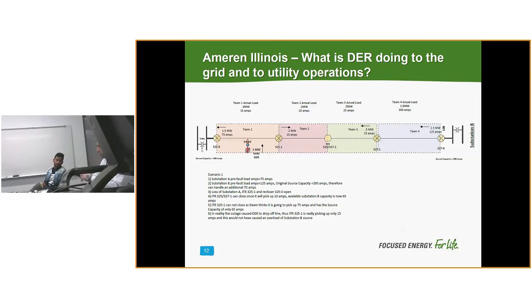And in particular, it used to be an anti-islanding rule or standard. The idea there is when you have an outage, you don't want all these DERs to still be connected to the system and trying to provide energy to the system. That creates an unsafe situation for workers on the grid. That's one. So anytime you see a disturbance on the system, the idea is to give ample time for the DER to drop offline. So it monitors frequency very closely, deviations in frequency very closely, and it monitors deviations in voltage very closely. And as those occur on the grid, the DER will drop offline within a certain amount of time, seconds, anytime it sees a disturbance, so it does not contribute more to the problem or add additional problems to what's going on the grid.